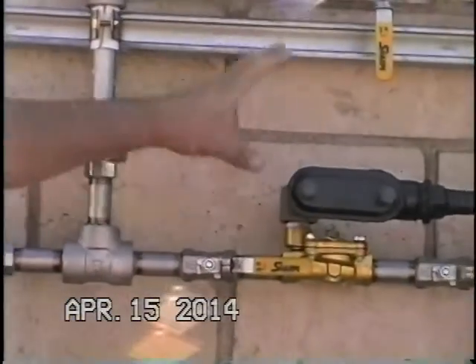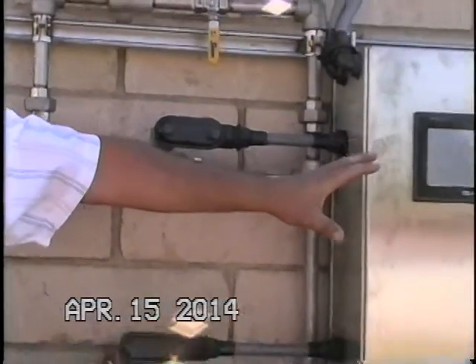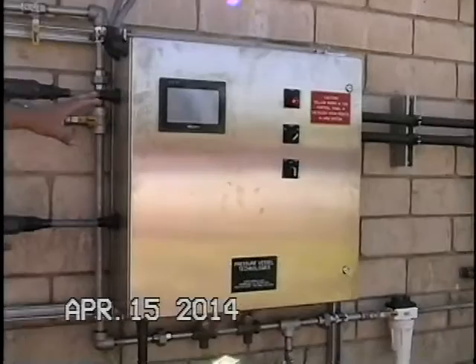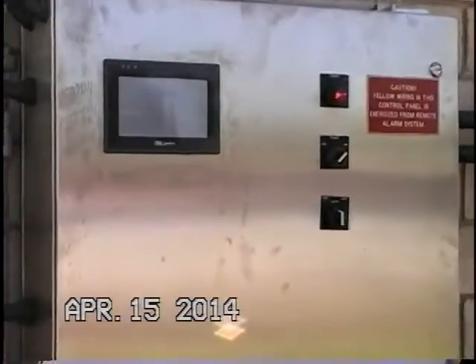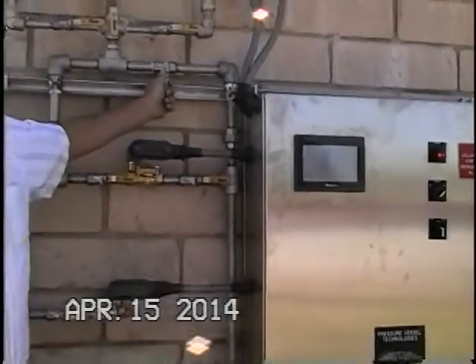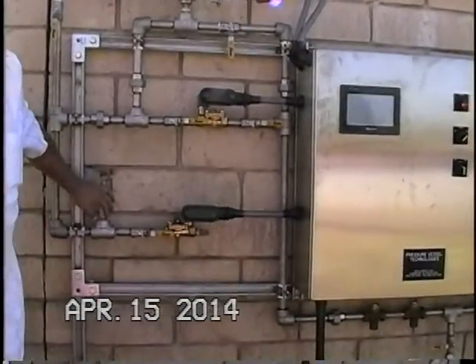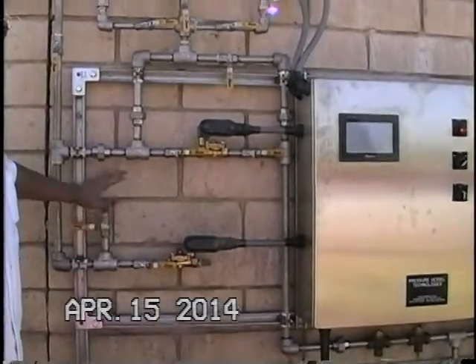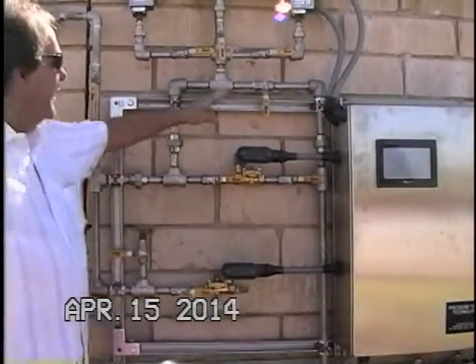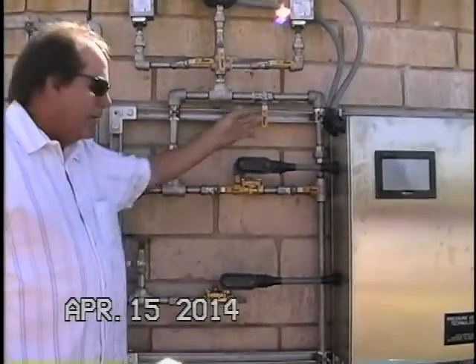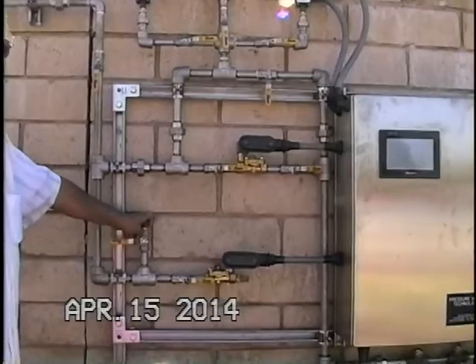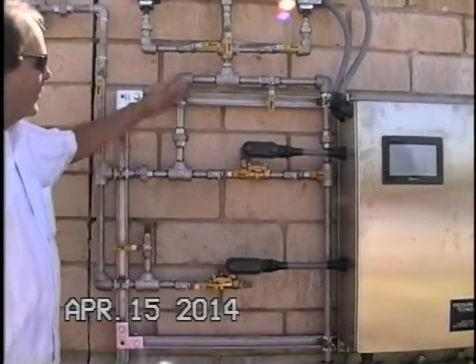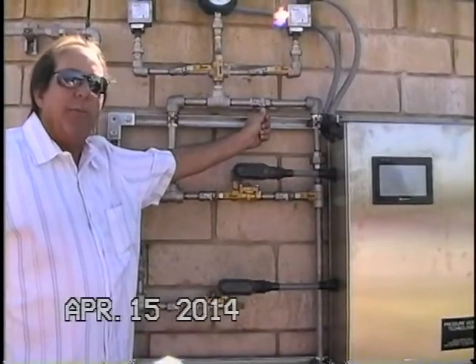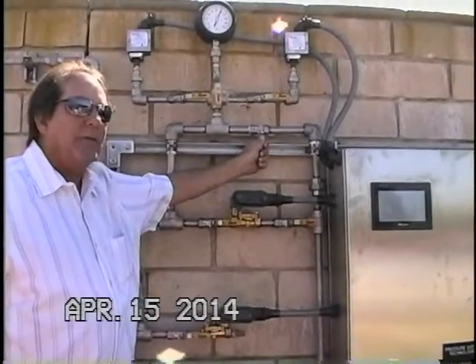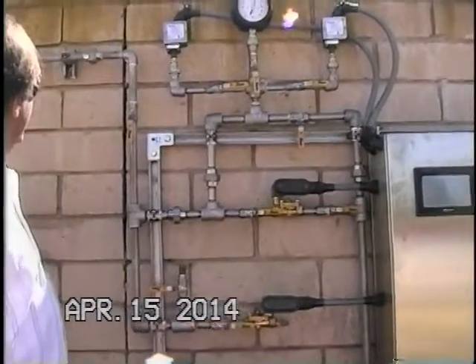This is your add air solenoid valve. Now, in every case, if this system ever went down, the control panel for any reason, you always have the opportunity to manually add air or manually vent air to change the liquid level inside the tank. This is your bypass line. This is your vent line, your manual vent. If you manually vent it, you're going to raise the liquid level. If you manually open it up, you're going to add air. You're going to push the liquid level back down. So that's part of your features here.